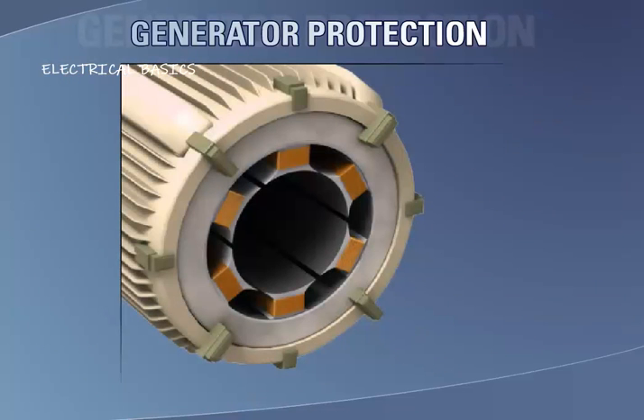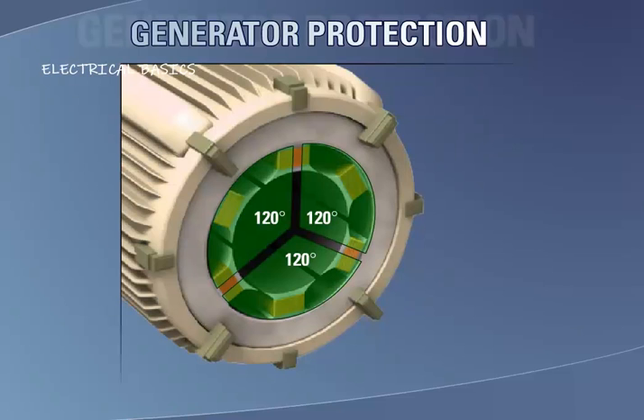Large utility class generators produce three-phase alternating current, and so our single-phase generator is modified with the addition of two more pole pairs. The poles would be positioned such that the pole pairs are directly opposite each other, and planes running through any two pairs of poles will intersect at an angle of 120 degrees. This arrangement of poles forms the stator of a two-pole, three-phase generator.